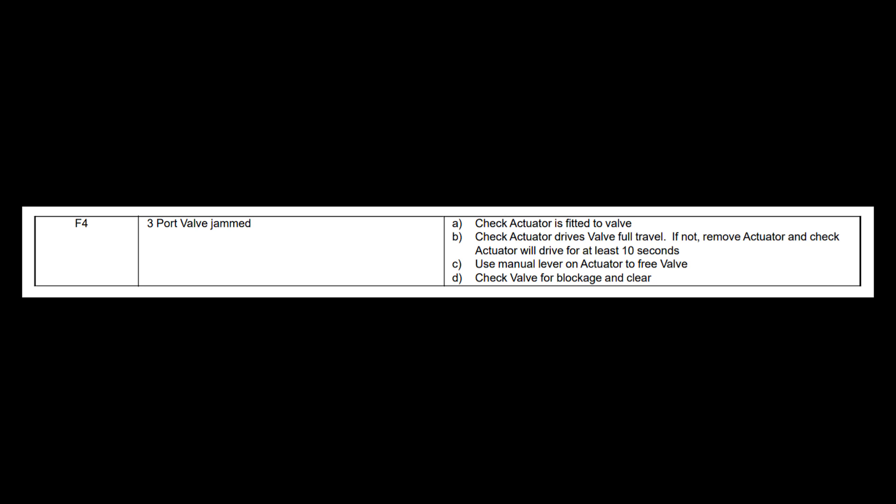It suggests: check the actuator is fitted to the valve, check the actuator drives valve full travel, if not, remove actuator and check actuator will drive for at least 10 seconds. Use manual lever on actuator to free valve. Check valve for blockage and clear.